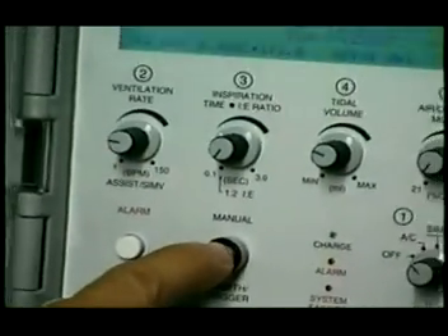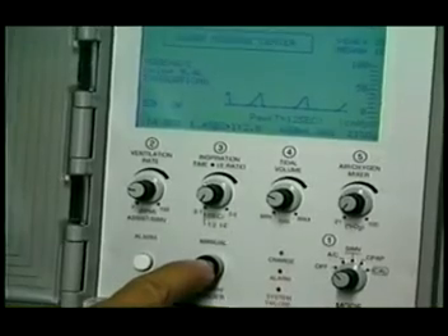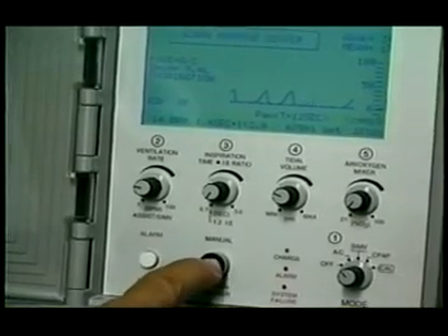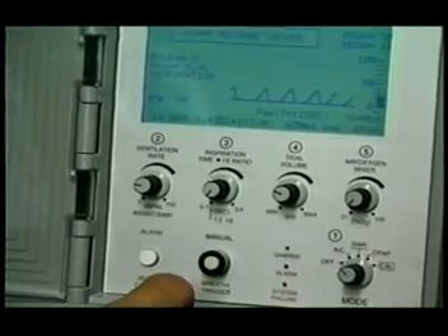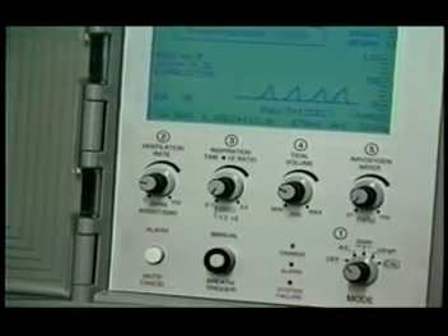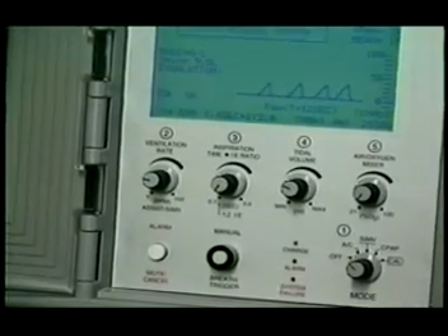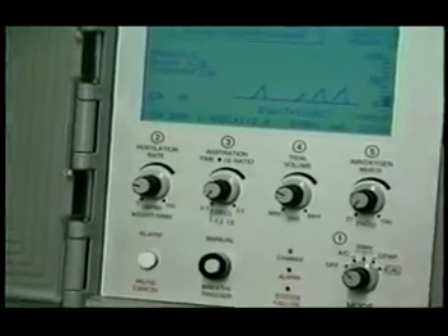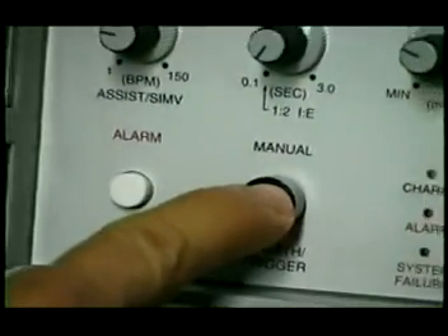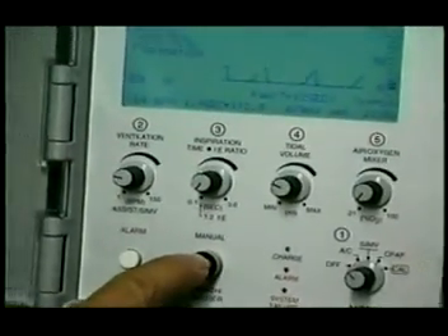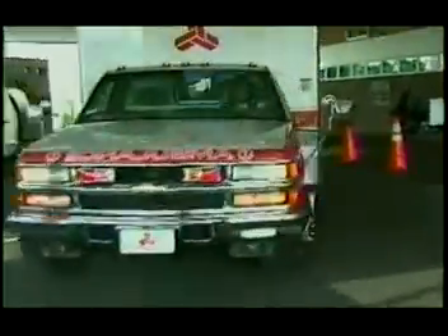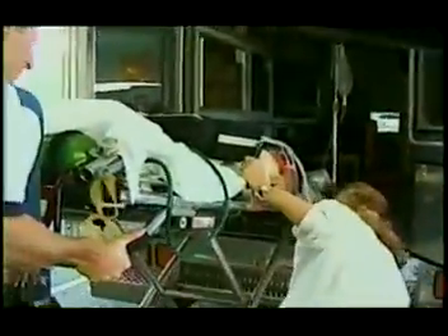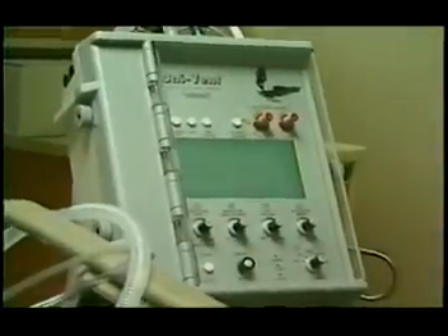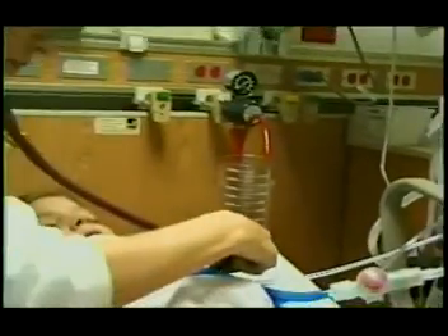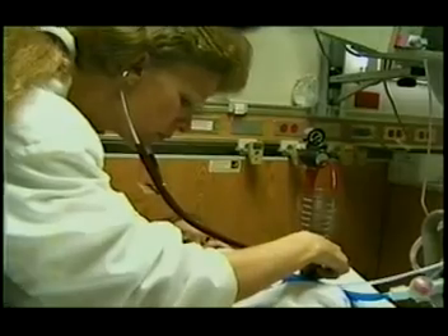The manual breath trigger push button has 2 functions. During normal ventilator operation, an additional measured breath is delivered at the current settings each time you press the push button. You can hyperventilate a patient by pressing this button or let the normal pre-existing ventilation rate resume. If there is a malfunction of the ventilator and the secondary or backup ventilator turns on, this push button becomes a manual trigger. It will allow gas to flow for as long as I press the push button. Gas flow to the patient is limited to 30 LPM and pressure limited to 40 centimeters of water.